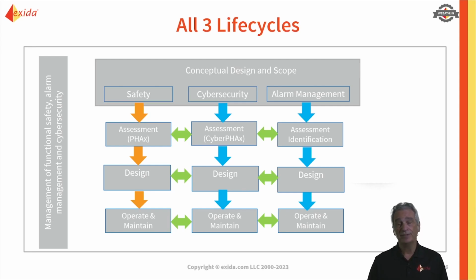And for the alarm management, the same thing. We still need to define what the requirements are. We need to create a master alarm database. That means we need some form of alarm philosophy that we want to follow, and then we use that to rationalize the alarms. And there's an ongoing process where we will periodically go back and do audits and make sure, if any alarms are added, is the master alarm database up to date or not? So these three have the same three life cycles.